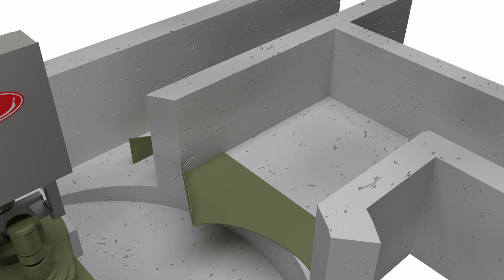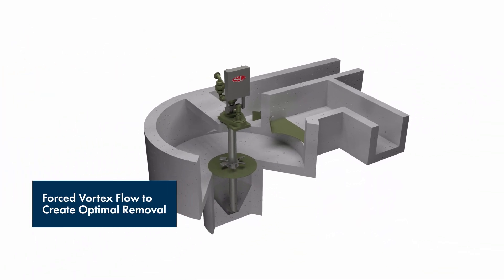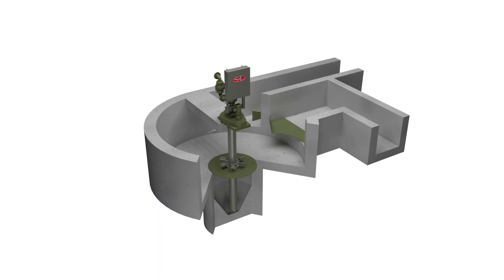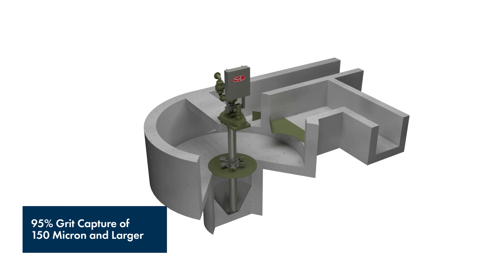It directs the inlet flow creating a forced vortex flow that prevents short-circuiting and allows for an extra full rotation through the chamber. This forced vortex action provides grit removal of 95% grit capture of 150 micron grit and larger.